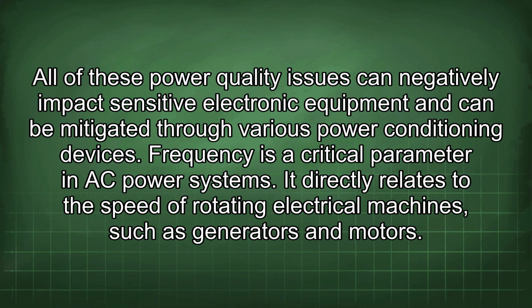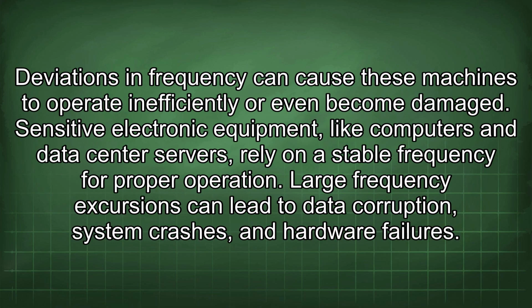It directly relates to the speed of rotating electrical machines such as generators and motors. Deviations in frequency can cause these machines to operate inefficiently or even become damaged. Sensitive electronic equipment, like computers and data center servers, rely on a stable frequency for proper operation. Large frequency excursions can lead to data corruption, system crashes, and hardware failures.